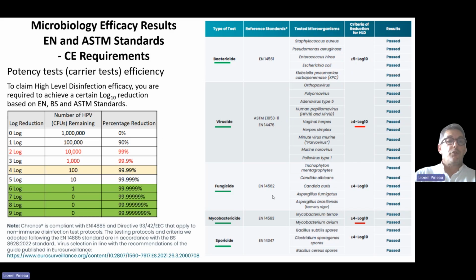For all carrier tests, to claim high-level disinfection, you have to demonstrate that you are able to achieve a certain log reduction based on the EN or the standard you use. And this log reduction may change from one microorganism to the other. For example, according to the EN regulation, you have to demonstrate a 5 log reduction in bacteria, whereas for viruses, you just have to demonstrate a 4 log reduction. As you can see on the right part of this slide, all tests done with the UVC disinfection process were compliant with the standard requirement. And we can clearly say that the Chronos unit reached the same efficacy level as what is required for a chemical disinfectant intended to be used for the disinfection of medical devices.